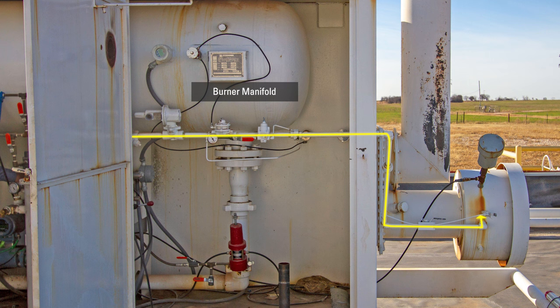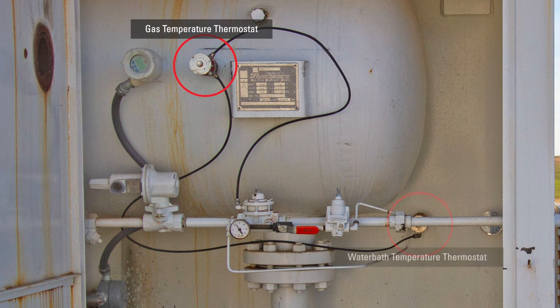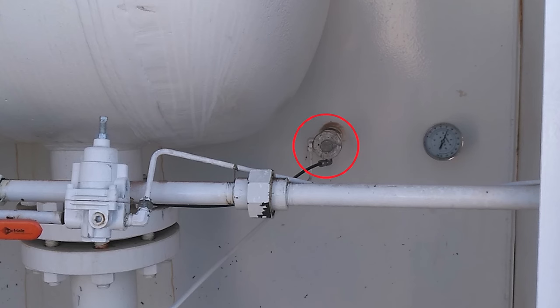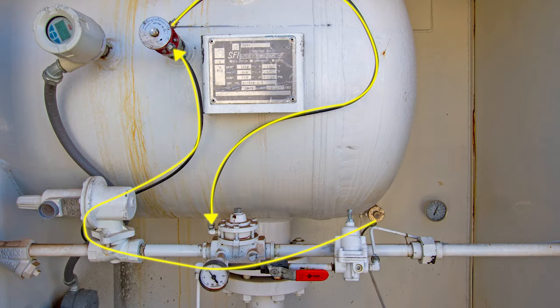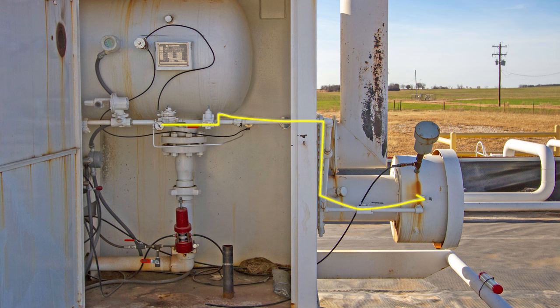This system is the burner manifold with two Kimray thermostats and one burner valve. One thermostat is monitoring gas temperature, the other monitors water bath temperature. If the set point of either thermostat is reached, gas going to the burner valve is shut off. The small tubing line coming off the burner valve supplies gas to the standing pilot light located in the flame arrester.